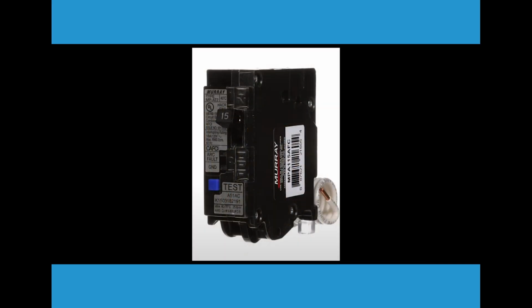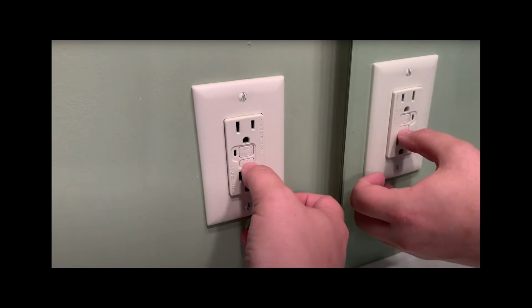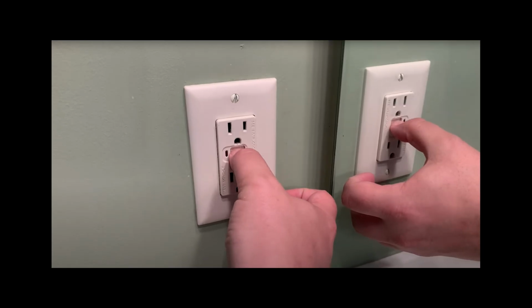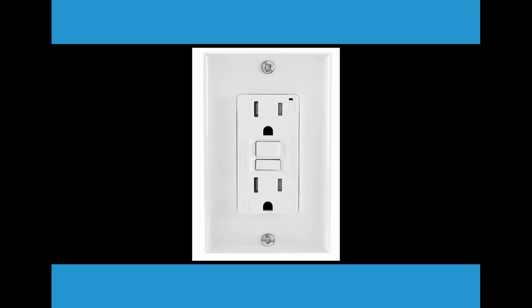However, if you were able to successfully reset your breaker, then all you need to do is ensure that your GFCI is also reset, and proceed with the previously mentioned process to determine which device is causing the trip.